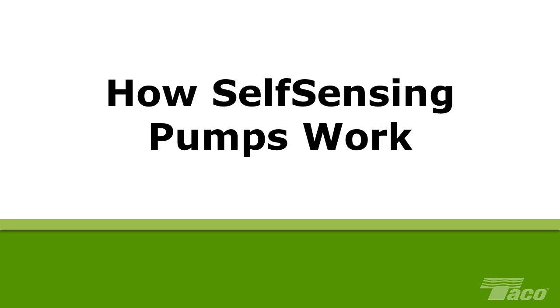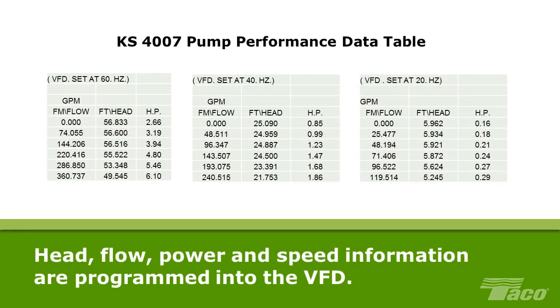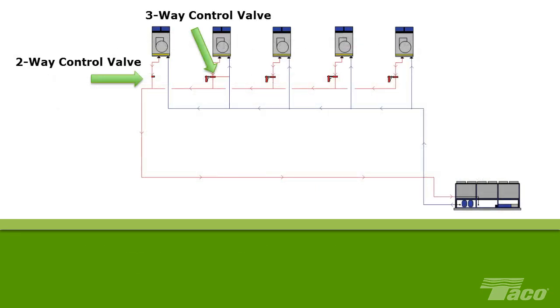How self-sensing pumps work. The key to the self-sensing pump's operation is the performance data that is collected before the pump leaves the factory. The head, flow, power, and speed information for each of the data points are programmed into the VFD. With this information in a lookup table within the VFD, the drive is now capable of operating at any flow and head within the range of the collected data table. Let's look at how the self-sensing pump responds to changes in system demand in our sample system.